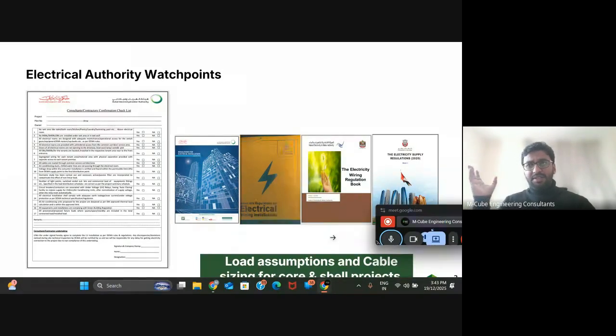We recently had a project which was designed completely for retail outlets. There were around 7 different retail outlets, like McDonald's and KFC. But the power requirement for each outlet was assumed to be only 10 kilowatts, 15 kilowatts, 12 kilowatts, or 7 kilowatts, which is very insufficient for these types of outlets to work on. So it had to go back into a reapproval process to ensure that proper loads were met, and then they had to reapply for the electrical load.